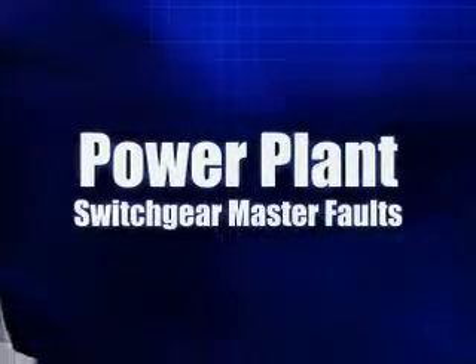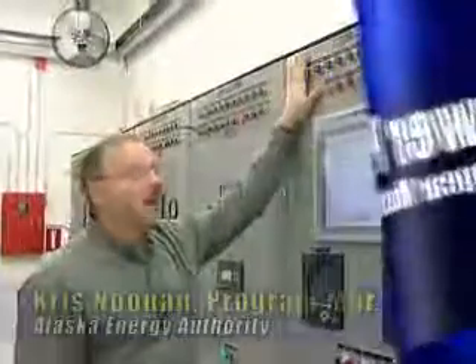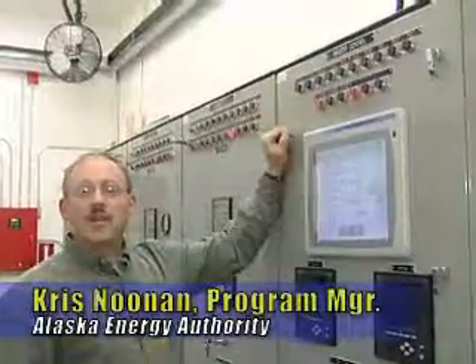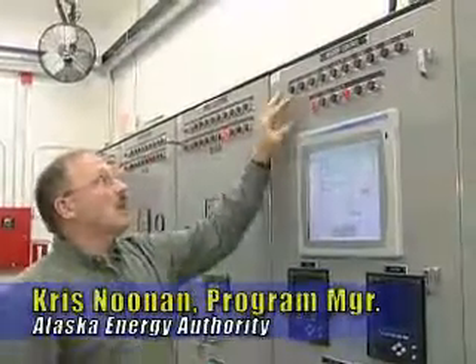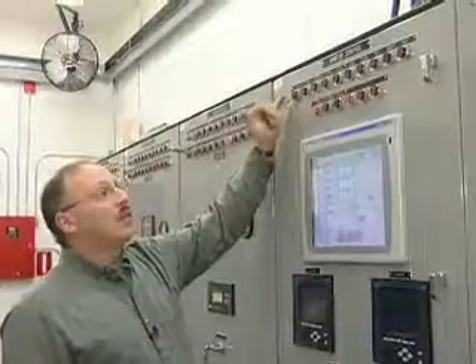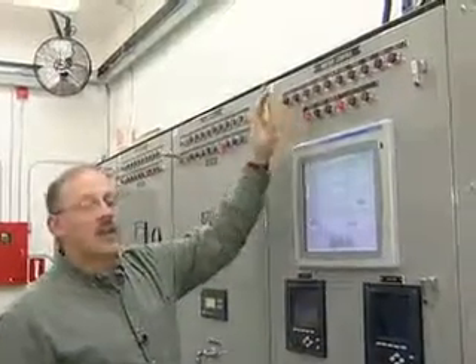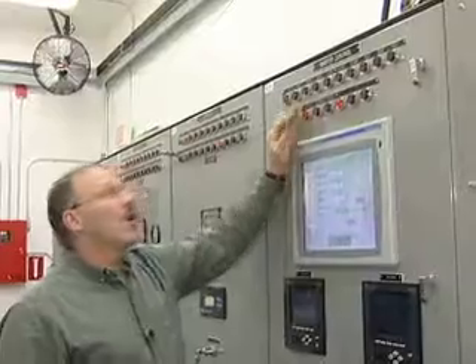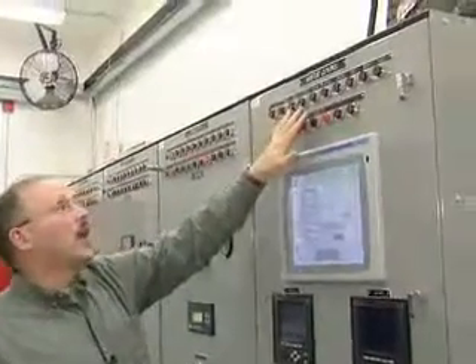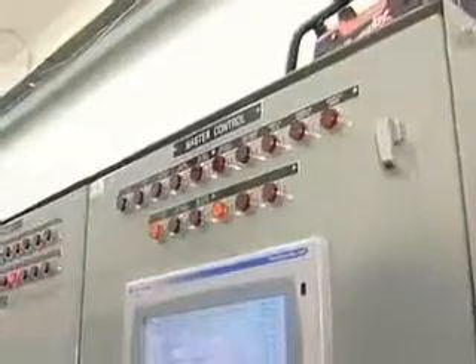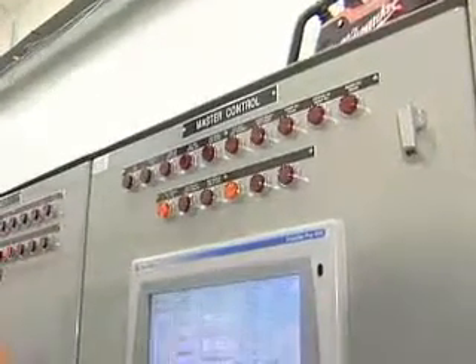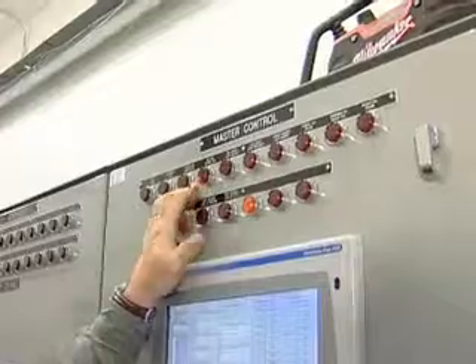We're going to talk a little bit more about the master control section here. We want to talk a little bit about these faults, how they work on the system. We talked earlier about when you get an indicator fault in the master section, it's going to shut the whole system down. Basically, all of our indicator lights are across here. The only one that will not shut down the system instantly is the low day tank level. Basically, we have a 2-hour timer built into that.